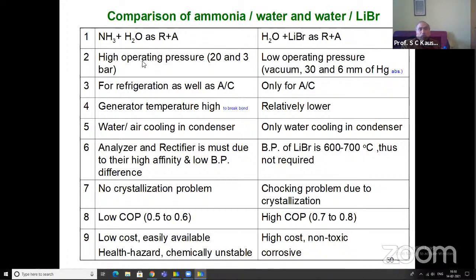Now here we have high operating pressures. Nearly, high pressure is 20 bar and low pressure is about 3 bar. Both are above atmospheric pressure, so we have the problem of high pressure vessels. In the case of water lithium bromide, we have low operating pressures, nearly 30 millimeter of Hg on the high pressure side and 6 millimeter of Hg on the low pressure side.